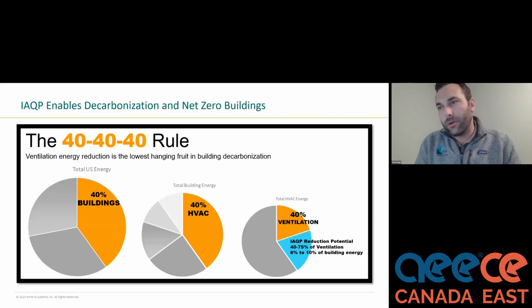So let's talk a little bit about decarbonization. These are rough numbers here, but we like to look at this as the 40-40-40 rule, which is ventilation energy reduction is definitely the lowest hanging fruit in terms of where we can get energy back on these buildings. In the United States, 40% of total energy consumption is from buildings, and within that, 40% of building energy is due to HVAC, and 40% of that is due to ventilation within that building. So there's a huge opportunity here to show 6 to 10% reduction in the total building energy by reducing outside air using the IAQp.